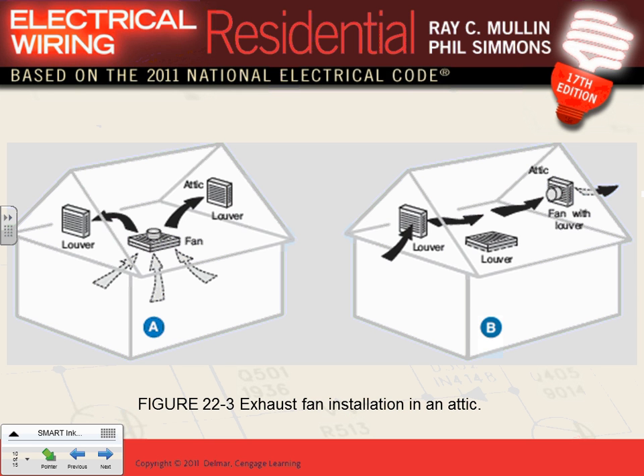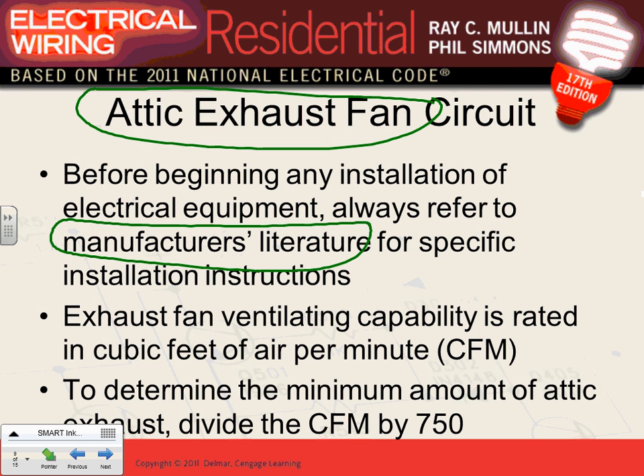You bring a dedicated circuit, typically, for that baby, and you wire it. All the control will be a thermostat that controls it. So if the temperature goes higher than a certain value, it will kick in. If the temperature goes to 90 or 100, it starts moving the air, and it continuously moves the air until it goes below a certain temperature, and it stops by itself. Any comments, guys, about this exhaust fan? So typically, a dedicated circuit to it with a switch next to it. You bring a dedicated circuit, a snap switch next to it as your disconnect, and hardwire it with a controller. Or the thermostat itself has an off position that qualifies it as a disconnect.